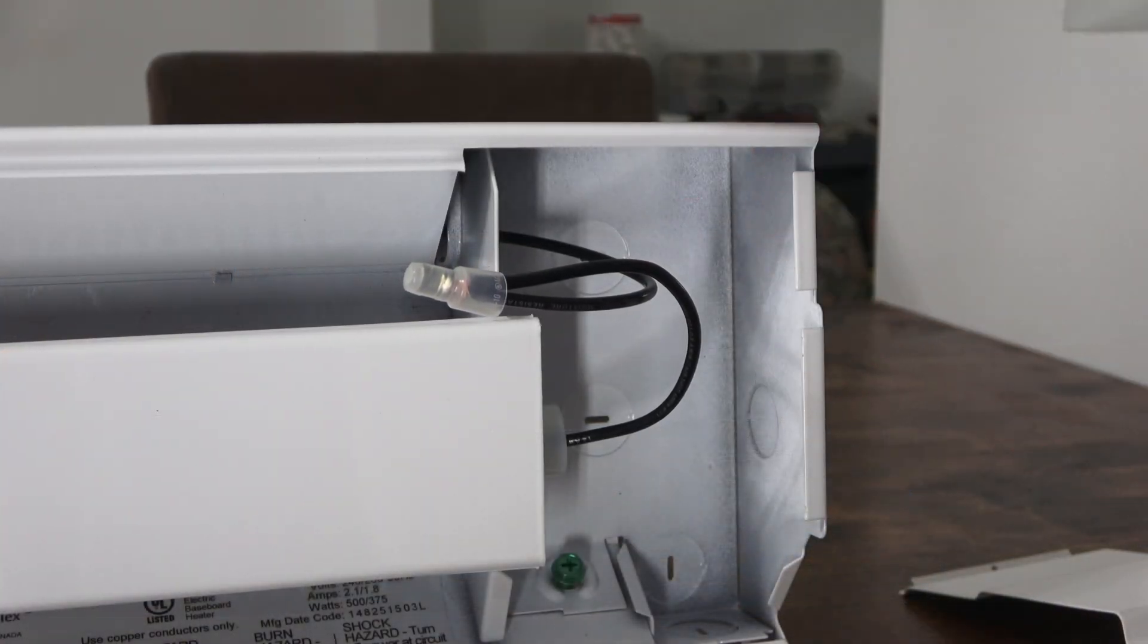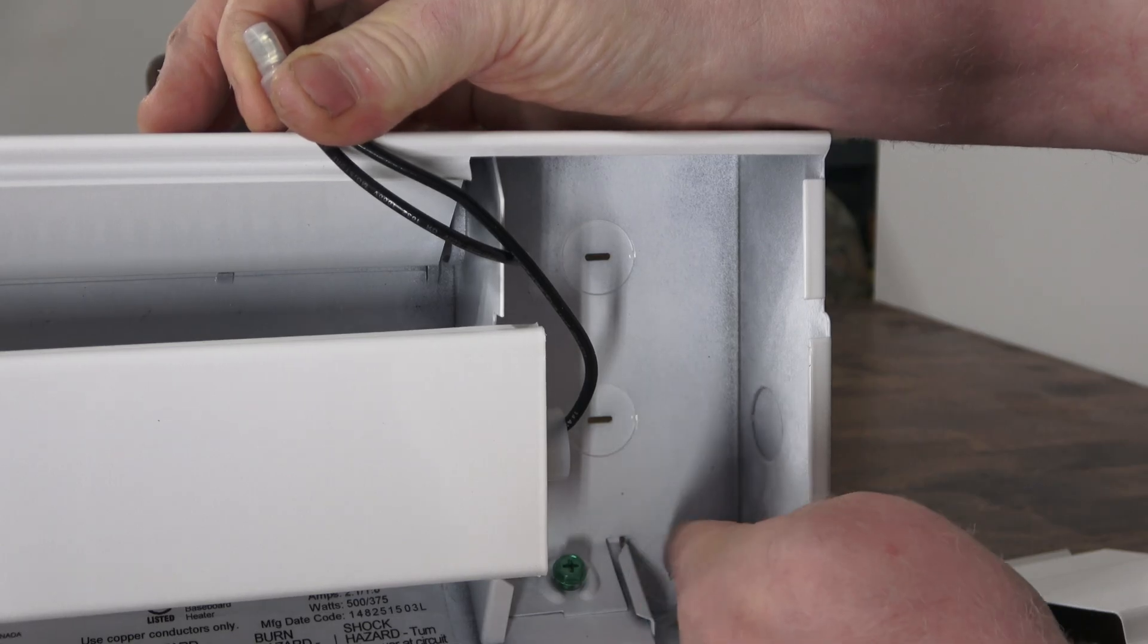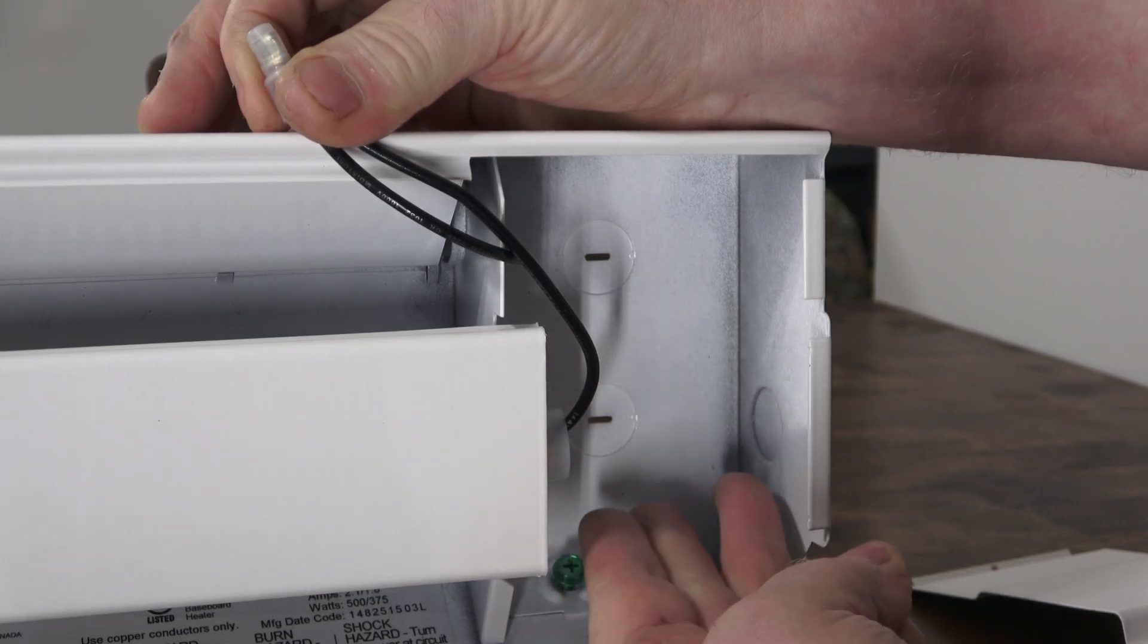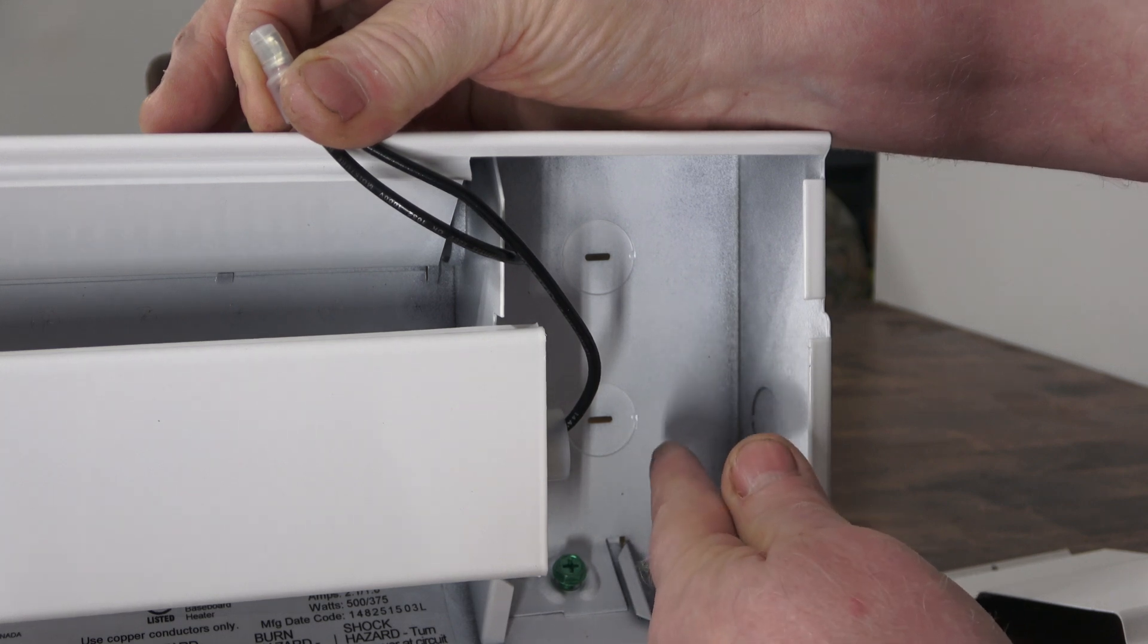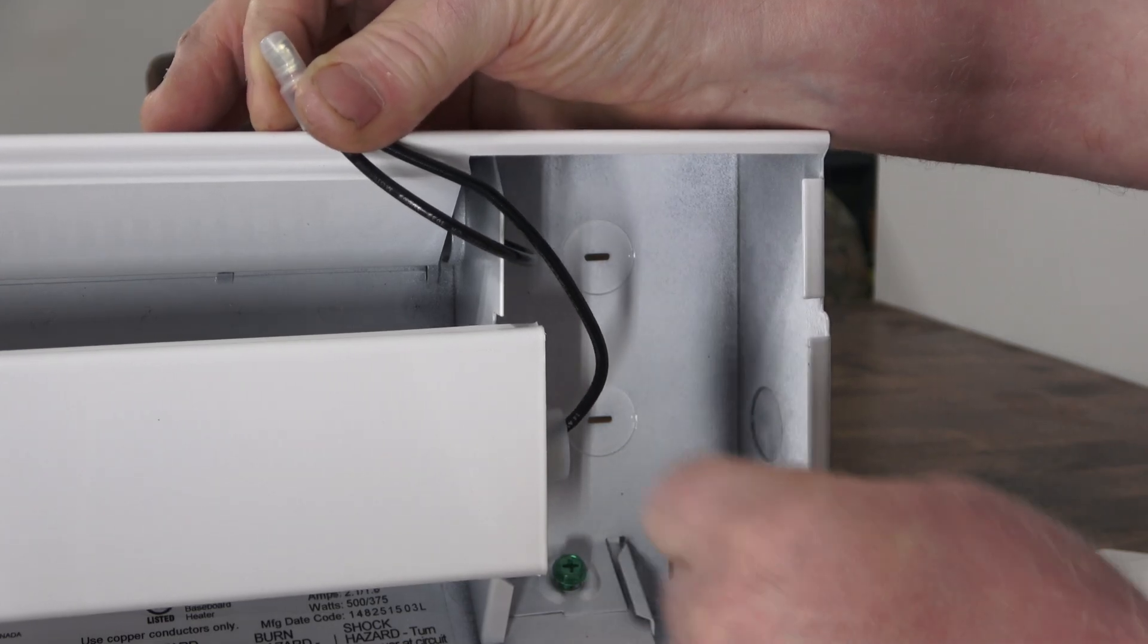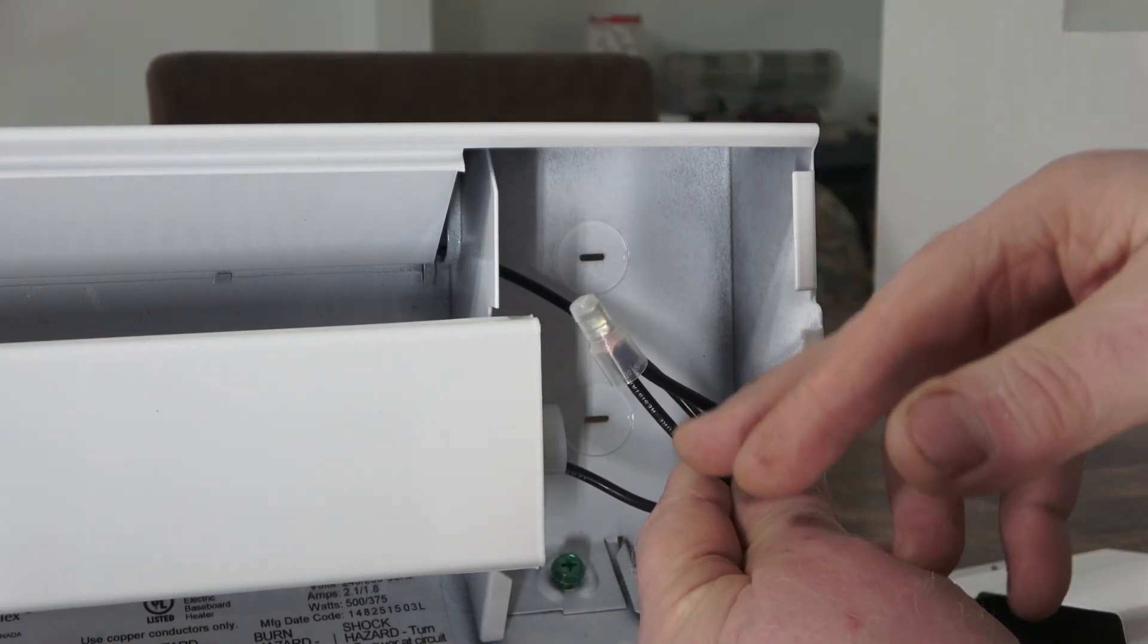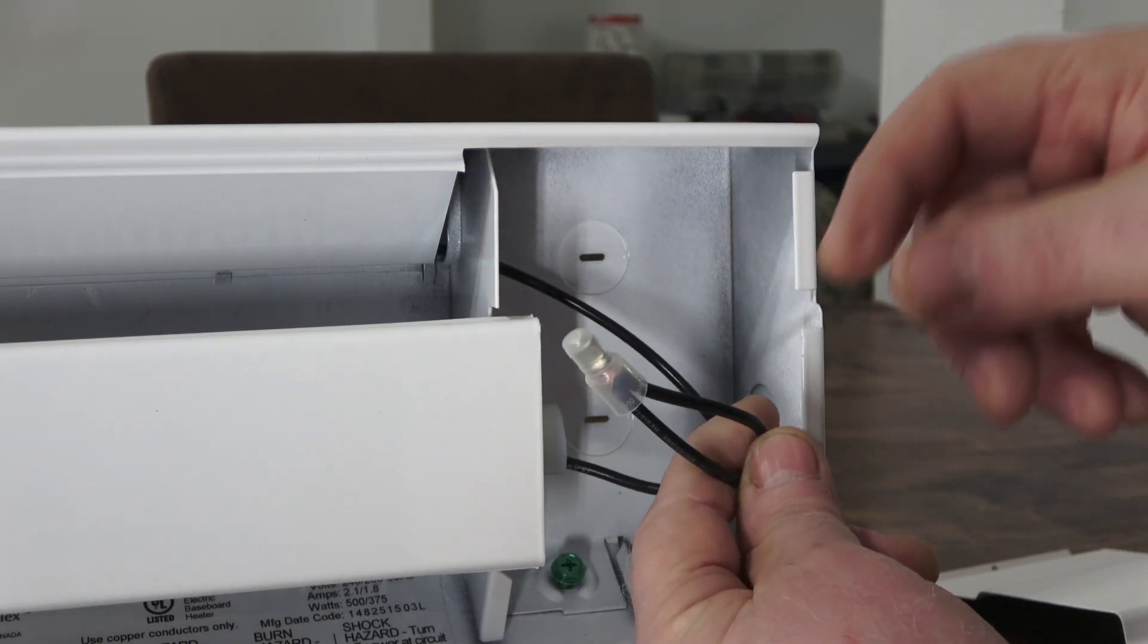The right side is the easiest. You would have your house current from the breaker panel coming through one of these openings with a Romex. Normally you'd have three wires. Two wires would be 120 volts on each leg, either red and black. Sometimes they use the white, I'll cover that later. And then a bare ground wire which goes on this lug. So you would snip this and put 120 volts to this wire and 120 to this one. And then you're done. The thermostat will turn the unit on and off.